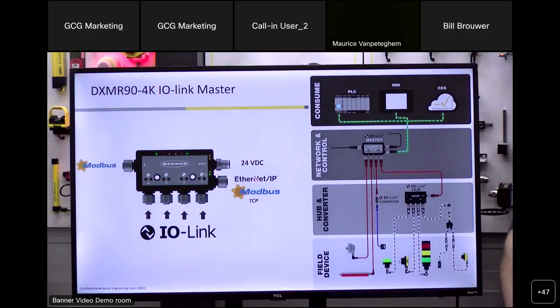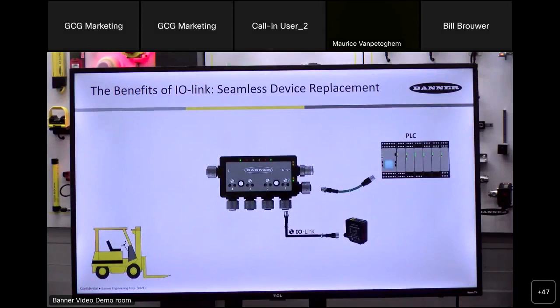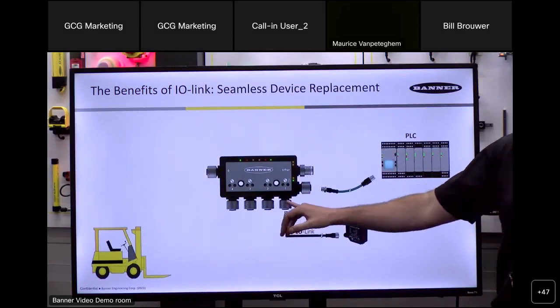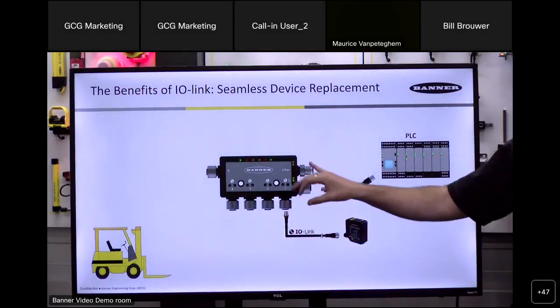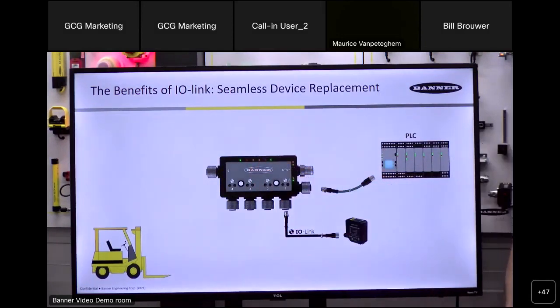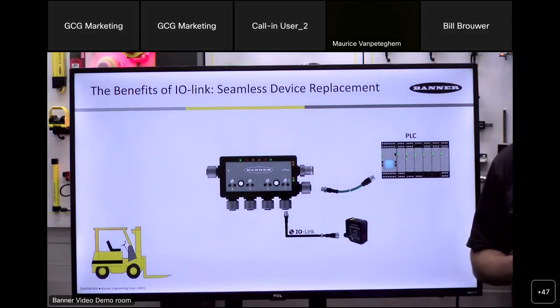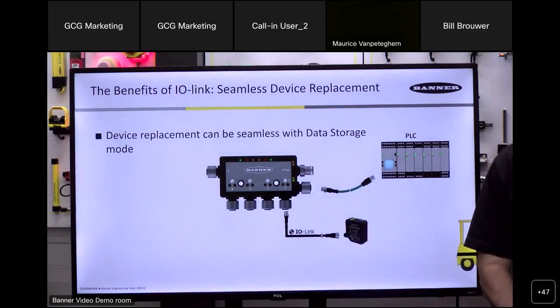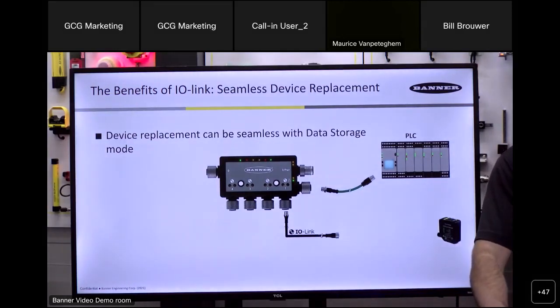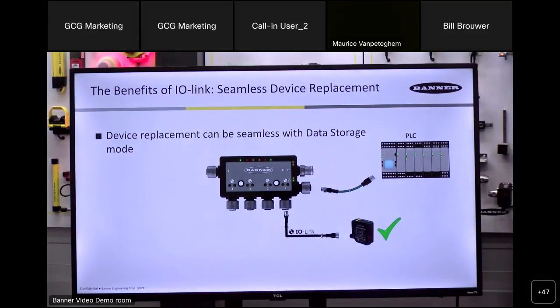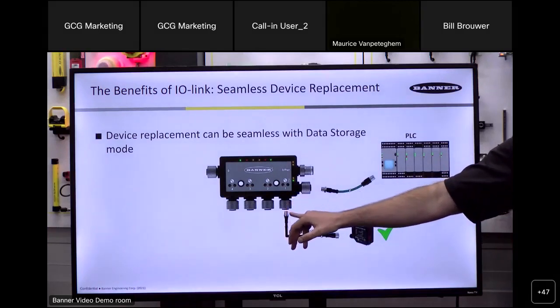Another benefit of IO-Link is what's called data storage mode, or backup and restore mode. You could actually store the configuration of your IO-Link device directly on the IO-Link master port. Many devices nowadays have programmable buttons, so you can have many different configurations, virtually infinite, where you set the range, the analog start point, the analog end point, the output behavior of the device. But what if you're in the field and a forklift driver runs over that device? With IO-Link data storage mode, you could simply plug in a new one, set it and forget it, making device replacement completely hands-off. It stores the device configuration directly in the port of the IO-Link master.